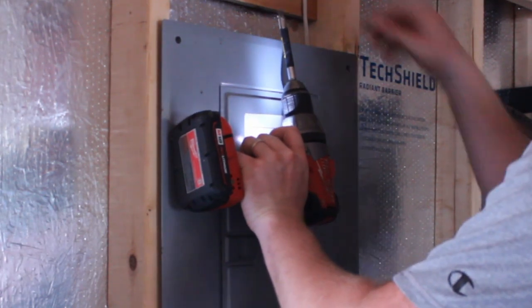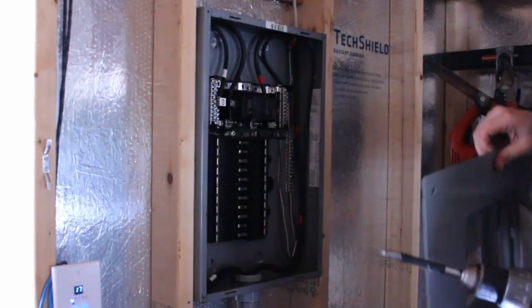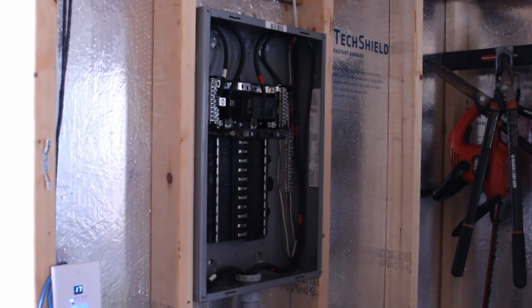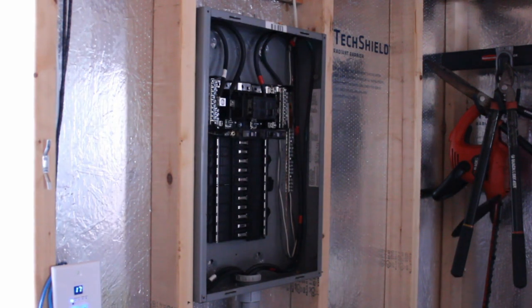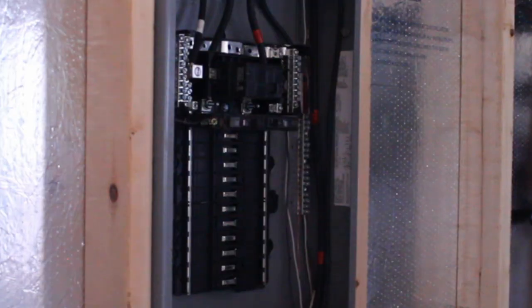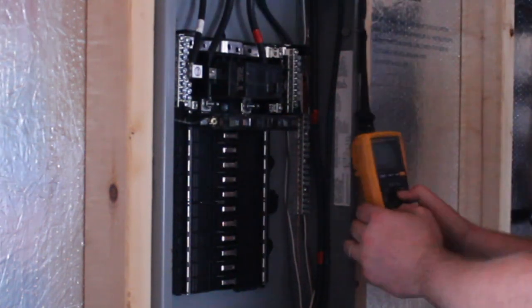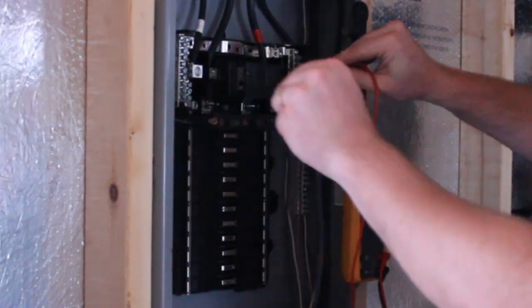Since I ran my power to a subpanel in the shed, I can turn off the entire panel with a breaker in my garage. This is much safer than simply turning off the main breaker in the subpanel and working around the feeder wire still alive. You'll see why in a bit.